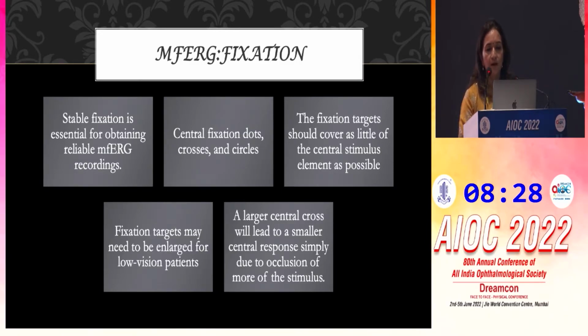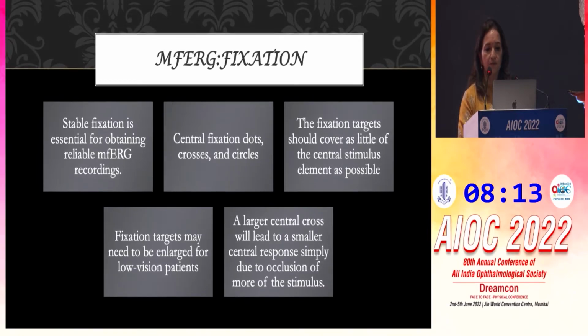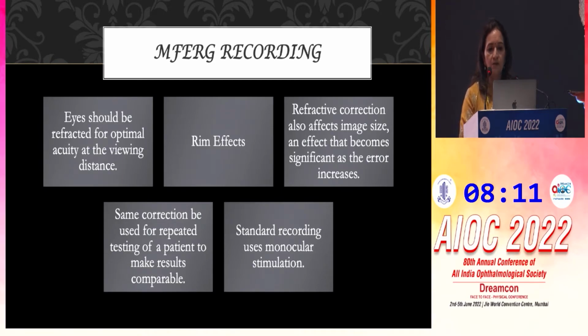So you have to monitor fixation. Most of the machines come with an automatic fixation monitor, and if that is not working, you will most likely give up multifocal ERG, because a little bit of change in fixation, if you are not able to monitor it, can change the multifocal ERG completely. This is because the patient is looking at a pattern, and the patient has to be corrected for the refractive error.